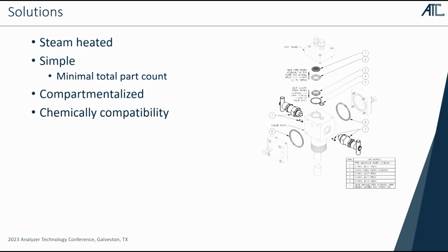So what have we done at Applied Analytics to help address this? We've developed our Pro 500 acid gas probe in part to specifically meet some of these criteria. It's a steam heated probe, and this works to prevent fouling and prevents the formation of acid dew points. It's above the acid dew point.